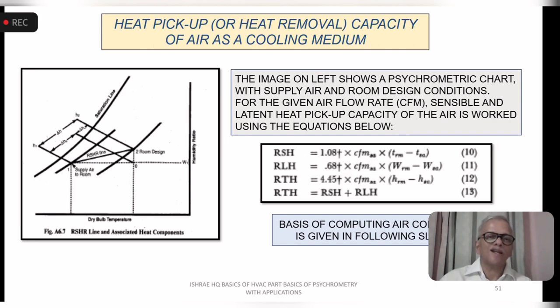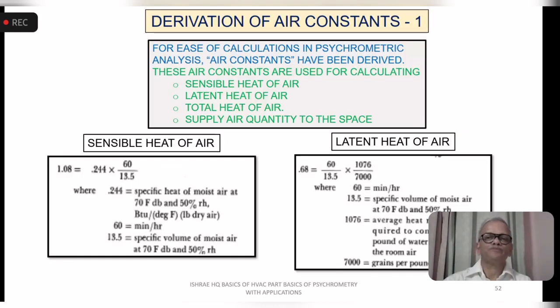You may have to increase the air quantity, because you cannot change the supply condition, since it is coming from the common air handling unit. So you will have to play with the air quantity only for a given space. There may be some spaces having higher sensible loads, and you will have to deal with that locally by giving additional air in the design. So that is the repetition of the computation of these constants.